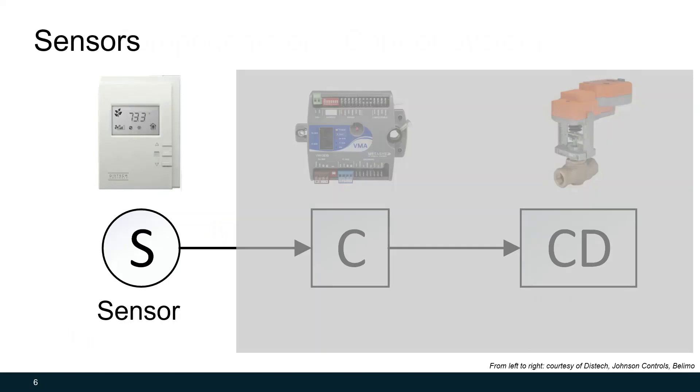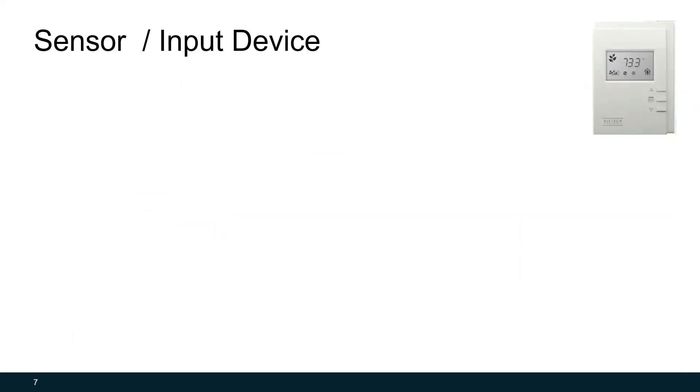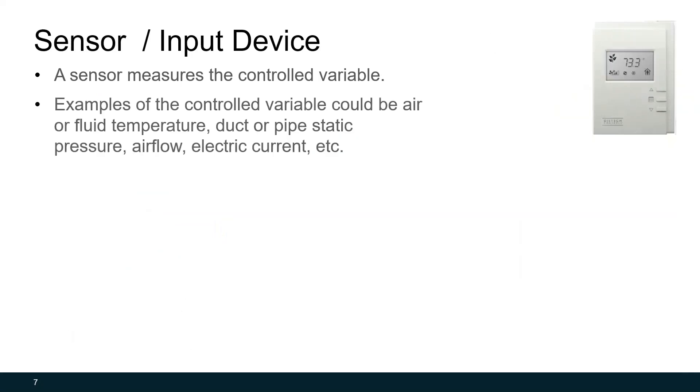So let's start with sensors or the input device. The sensor is simply a device that measures a controlled variable. What's the controlled variable? Well, for the thermostat that's shown in the top right of the screen, that's space temperature. It's simply whatever we're trying to measure and usually control in the building. It could be air temperature, it could be water or fluid temperature, duct or pipe static pressure, airflow through a duct, or electric current that's going to a piece of equipment.